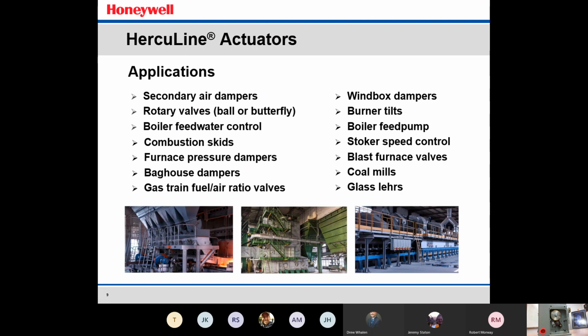Bag house dampers, gas trains, fuel air ratio control, wind box dampers, burner tilts. Burner tilts are big in the large power utility plants that require very high torque in order to do the burner tilt. These would be typically on tangent fired boilers, where they're tilting the burners to get better firing out of the burner box. Boiler feed pumps, stoker speed control, blast furnaces. So you can see these environments are typically pretty harsh industrial type environments and require something a little bit better than commercial style actuators such as a mod motor or some of the lower torque actuators.